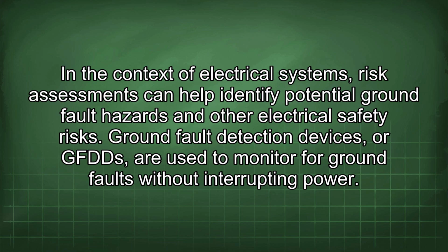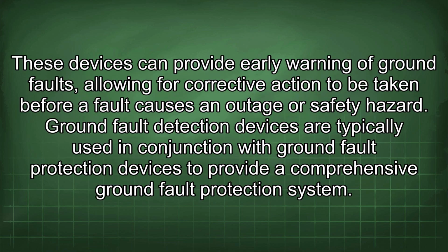Ground fault detection devices, or GFDDs, are used to monitor for ground faults without interrupting power. These devices can provide early warning of ground faults, allowing for corrective action to be taken before a fault causes an outage or safety hazard. Ground fault detection devices are typically used in conjunction with ground fault protection devices to provide a comprehensive ground fault protection system.